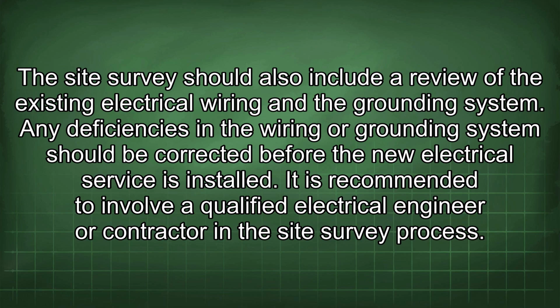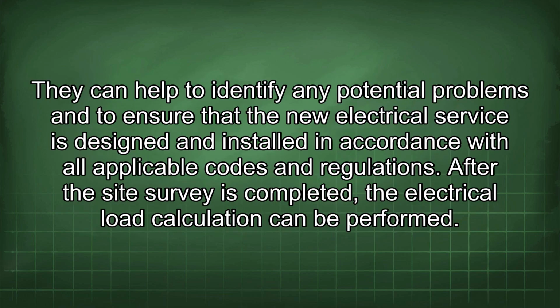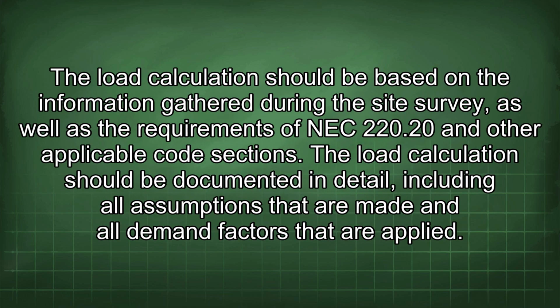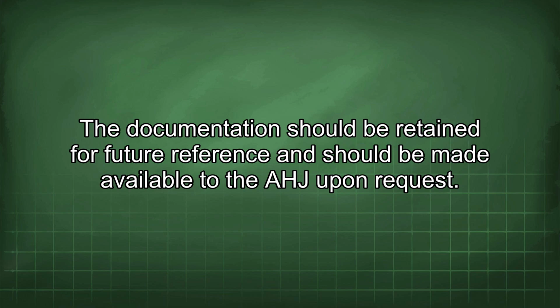It is recommended to involve a qualified electrical engineer or contractor in the site survey process. They can help to identify any potential problems and to ensure that the new electrical service is designed and installed in accordance with all applicable codes and regulations. After the site survey is completed, the electrical load calculation can be performed. The load calculation should be based on the information gathered during the site survey, as well as the requirements of NEC 220.20 and other applicable code sections. The load calculation should be documented in detail, including all assumptions that are made and all demand factors that are applied. The documentation should be retained for future reference and should be made available to the AHJ upon request.